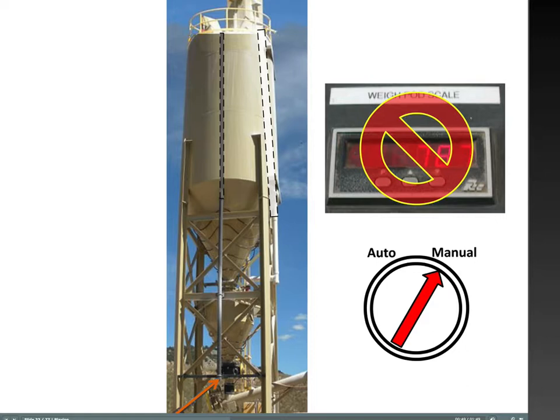Normally, the weigh pod is vented to atmosphere through the baghouse. This does not happen with the high air volumes used to pneumatically convey the material into the silo. The resulting back pressure is now fed back through the vent pipe, causing the weigh pod scale to increase significantly. Consequently, a smooth and accurate flow rate is no longer being indicated.